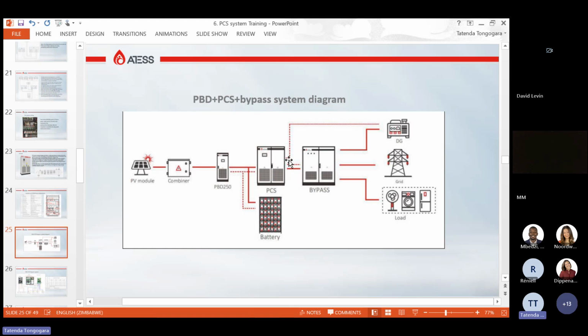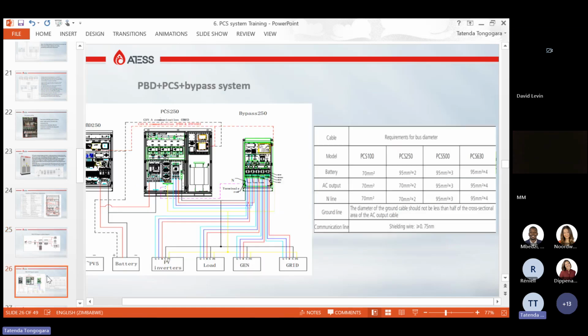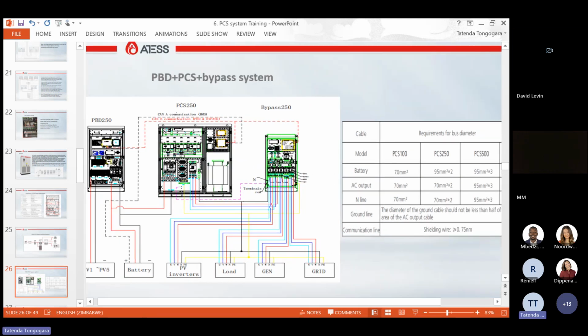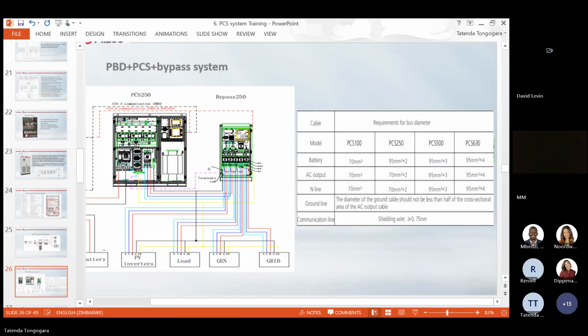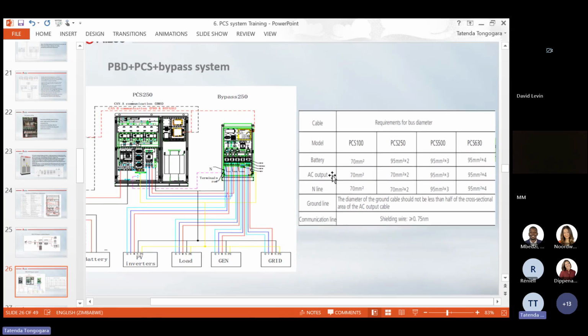So in the event that this is the PCS 500, the isolation transformer is a standalone component. So you have to connect the isolation transformer here. This is the simple diagram for PCS 250. I will show you how you connect your transformer. So, cable requirements: PCS 500 battery, 95 square millimeter cable, 95 by 3. These are the recommended cable sizes.